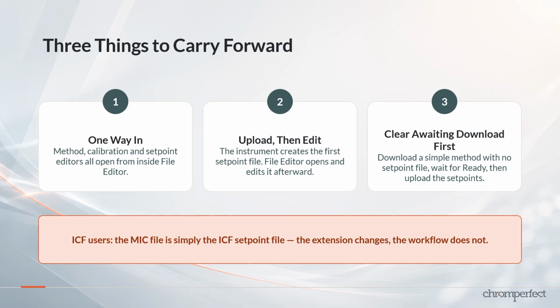This distinction is important because it prevents users from looking for programs that do not appear as separate user-facing applications, and it prevents them from trying to create setpoint files in the wrong order. For ICF users, remember that the MIC file is simply the ICF setpoint file. You still start from Chromperfect File Editor when opening or editing it. For other digitally controlled instruments, the file extension may be different, but the general principle is the same. Use the instrument to create the first setpoint file by upload. Use File Editor to open and edit the setpoint file afterward.